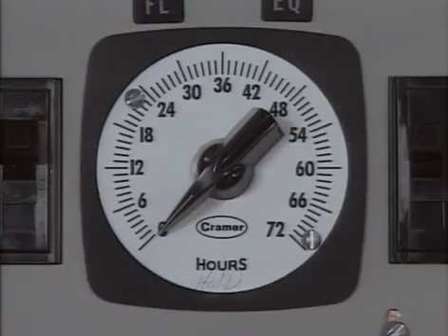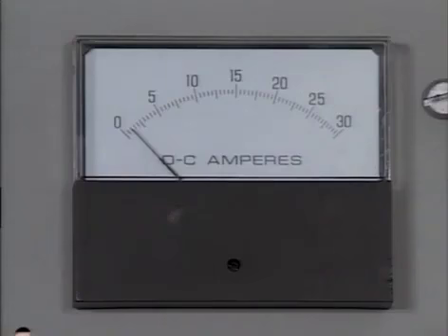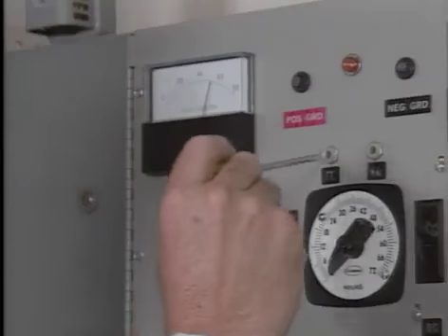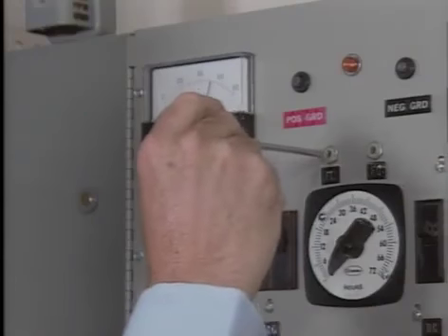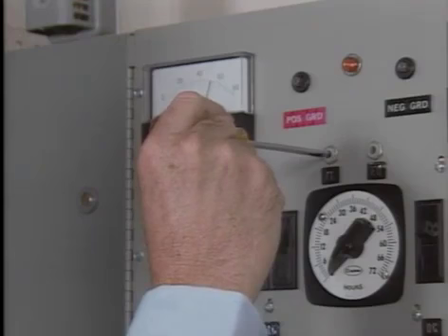The voltage is checked with the charger in the float charge mode. In addition, the charger output current should be close to zero, indicating that the battery is not discharging. If necessary, the float voltage potentiometer is adjusted to provide the required float voltage output to the battery.